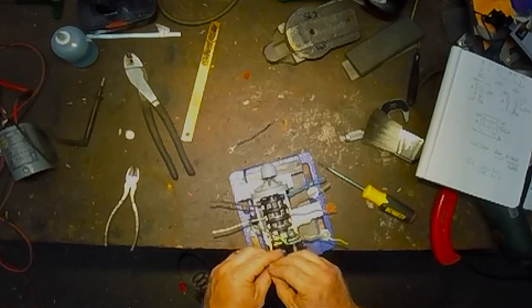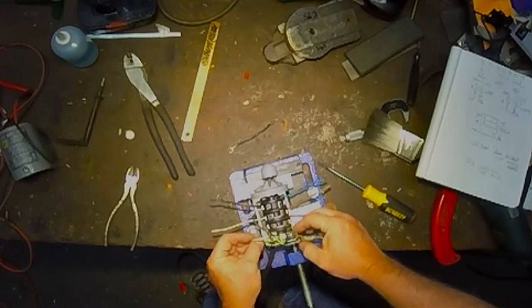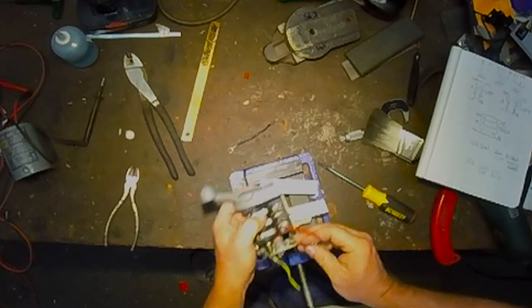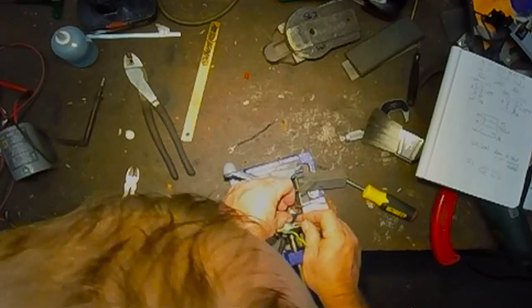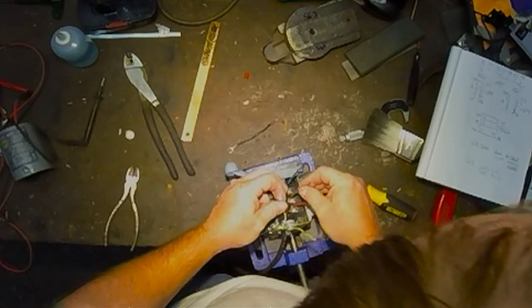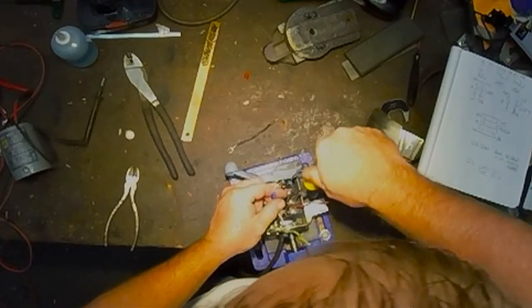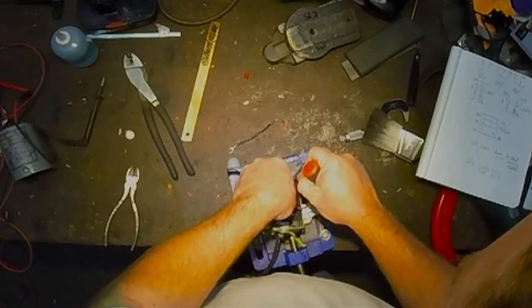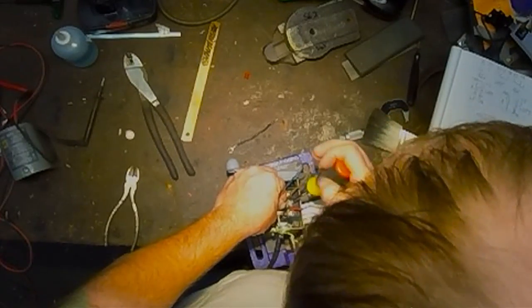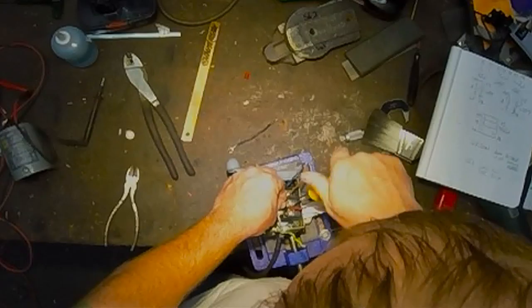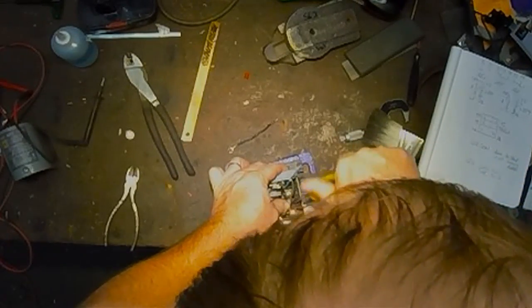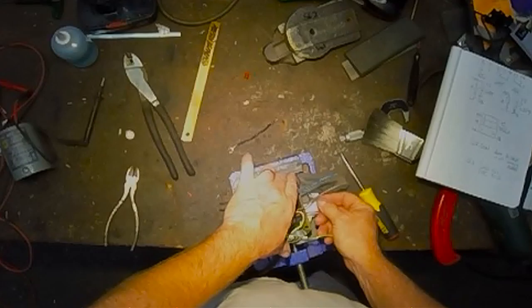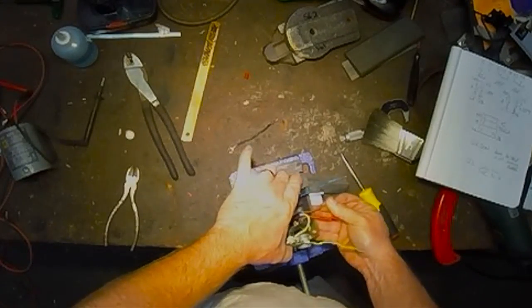How I'm going to do this now is we're going to make our line 2 connection over here. The hitch with this one is we have to connect it with the wire from T4, the motor terminal T4. We're going to do that by loosening up this spade terminal and this other one a little bit. Okay, so our L2 and T4 is on terminal 4.